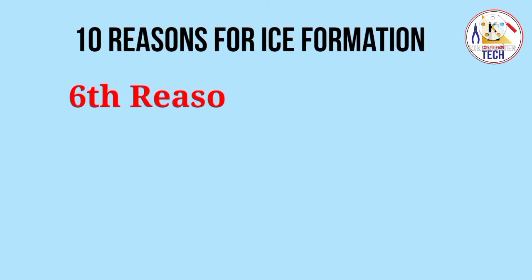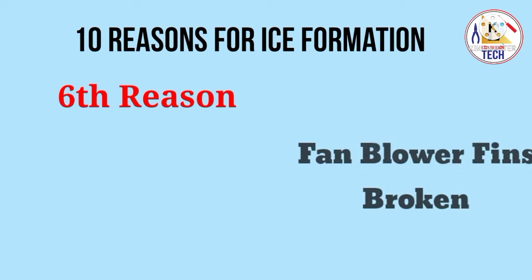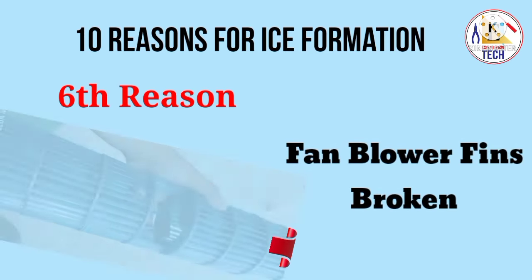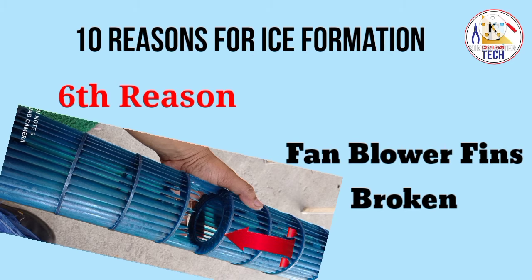The sixth reason for ice formation is broken fan blower fins. The fan which rotates in our indoor unit — if the fins are broken, it doesn't supply proper air, and at that time the evaporator gets ice formation. To avoid this, check if your blower fins are broken, as that is also a cause of ice formation.